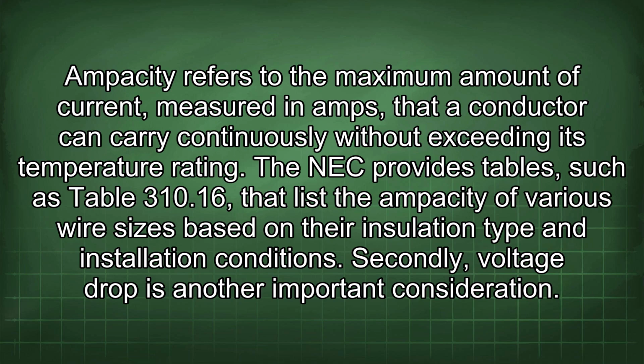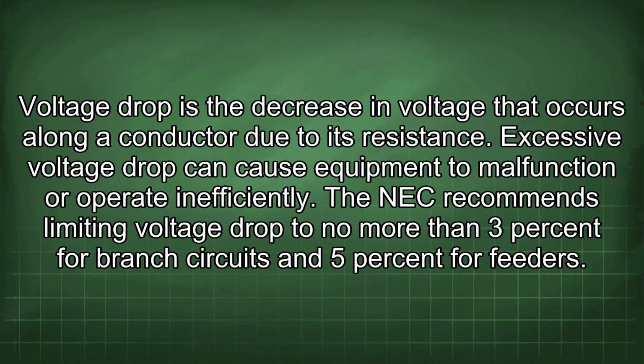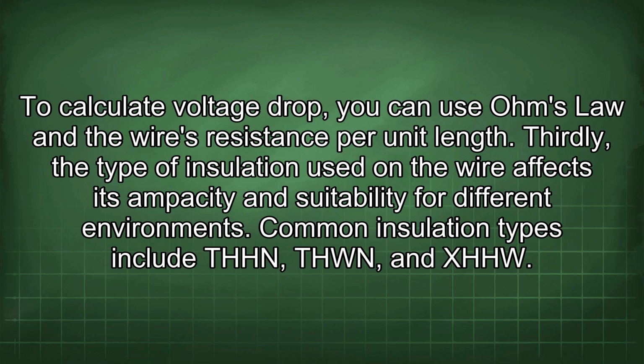Secondly, voltage drop is another important consideration. Voltage drop is the decrease in voltage that occurs along a conductor due to its resistance. Excessive voltage drop can cause equipment to malfunction or operate inefficiently. The NEC recommends limiting voltage drop to no more than 3% for branch circuits and 5% for feeders. To calculate voltage drop, you can use Ohm's law and the wire's resistance per unit length.